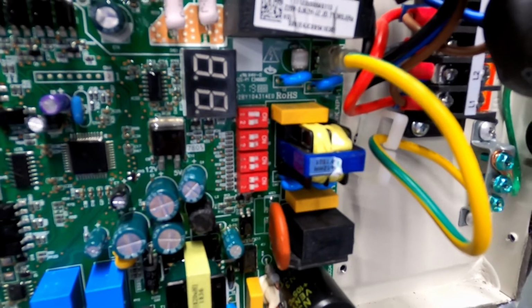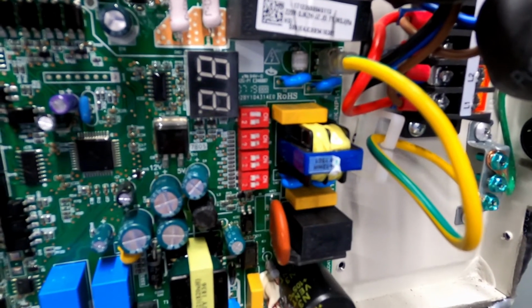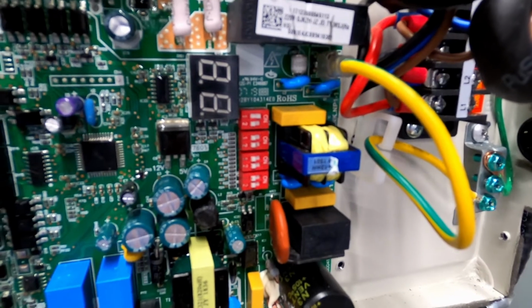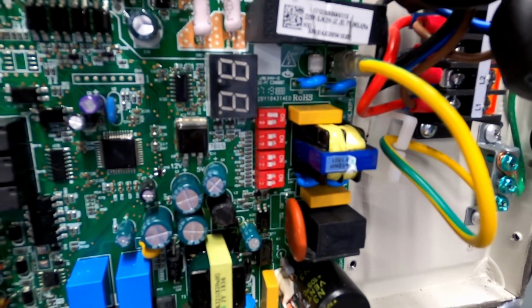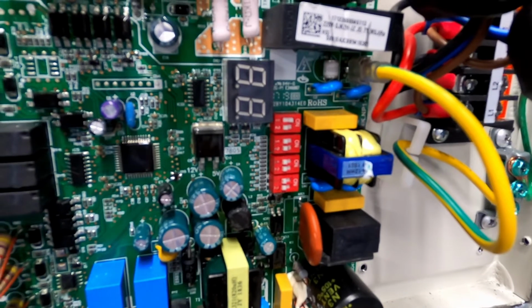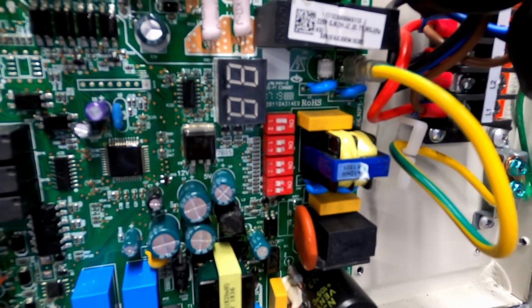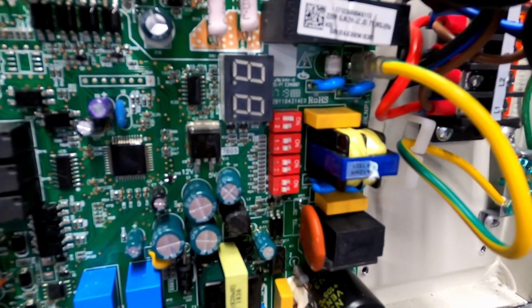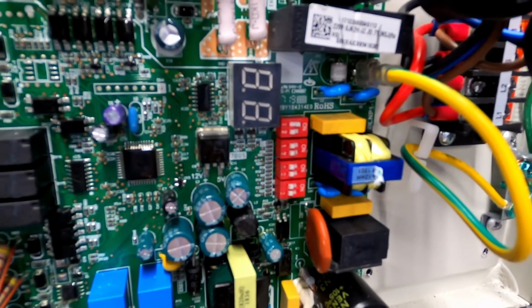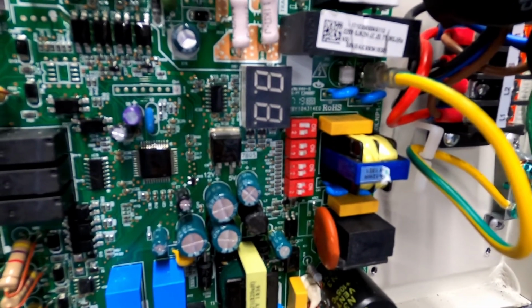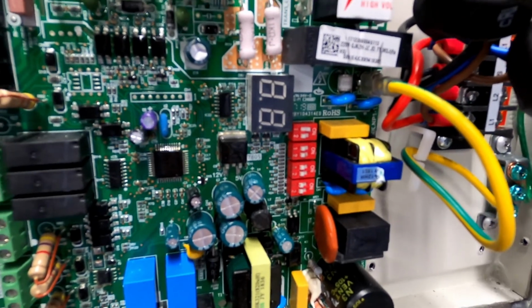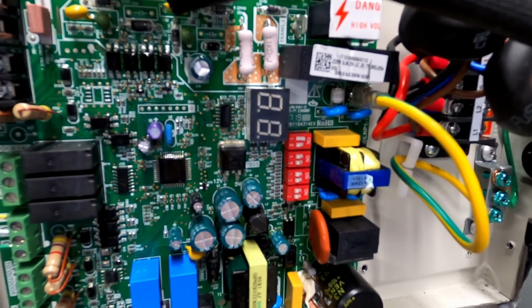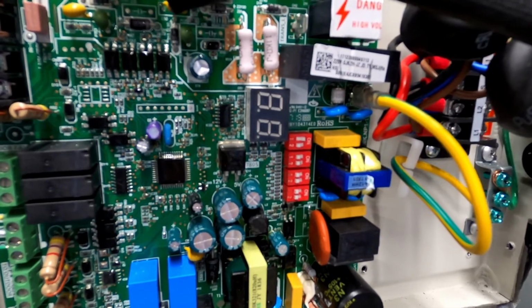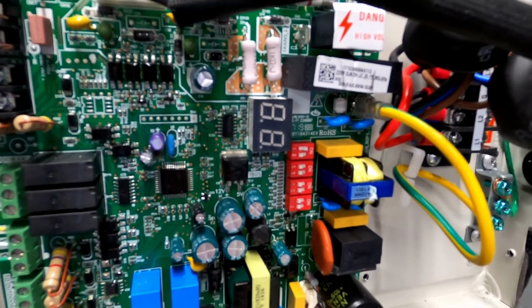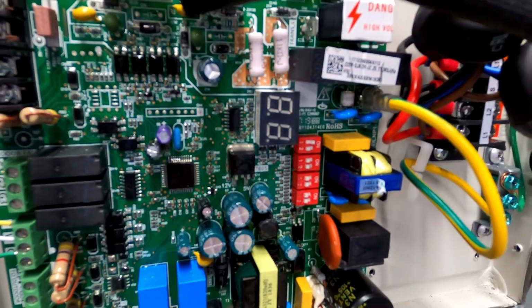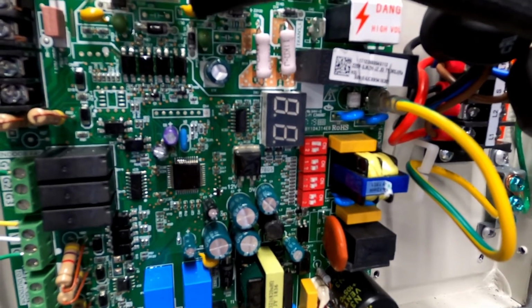SW1-2 needs to be off. That's important in this scenario with the hybrid combination because we don't have a communicating ductless indoor unit. So we'll make sure that SW1-2 is off. Dip switch 2-1 should be off because we have a heat pump. Dip switch 2-2 should also be off. This will allow the indoor fan to stop when the unit is in defrost mode or the coil is too cold and heating.